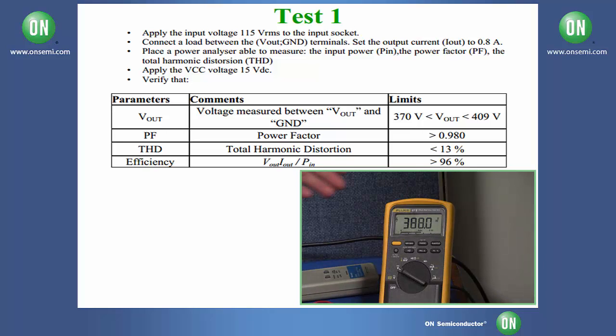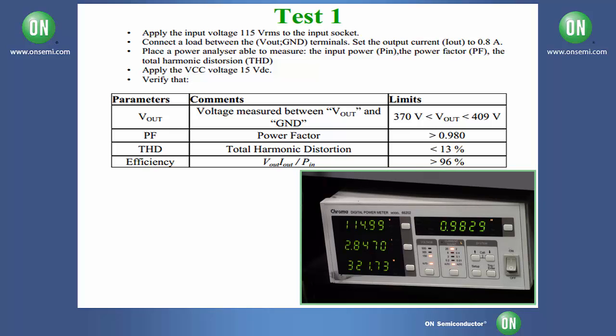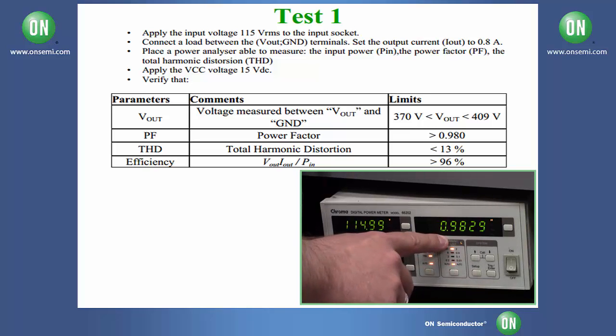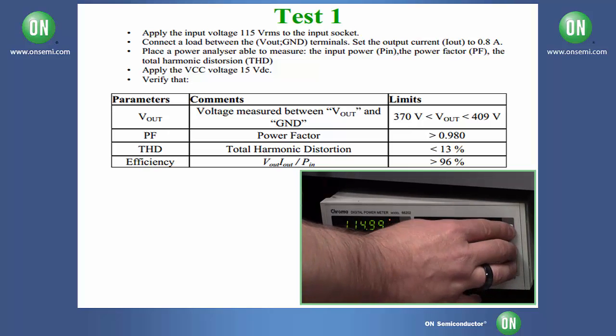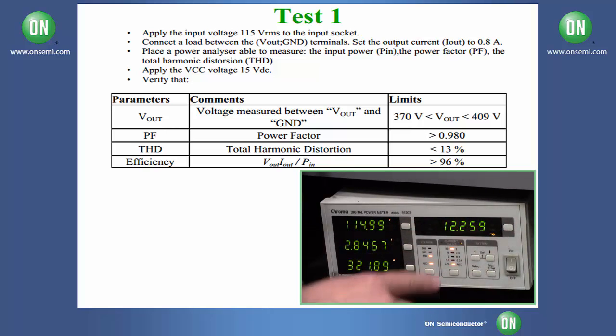And here we can see that we have our PFC output of between 370 and 409 volts DC. And next we're going to make sure that our power factor is over 0.98, which it is. And then next we're going to make sure that our THD is below 13%, which it also is. And lastly, we'll calculate our efficiency, which in this case turns out to be approximately 96%, which is acceptable. And this concludes test 1.